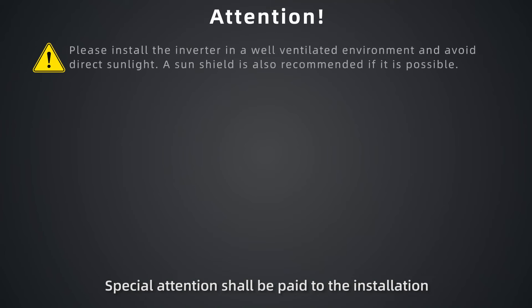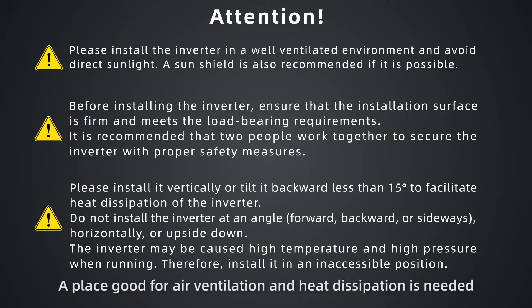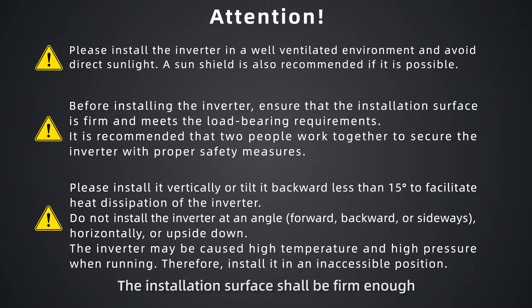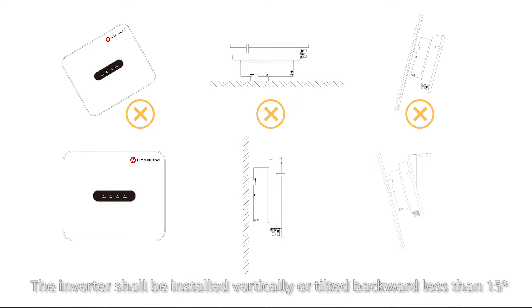Special attention shall be paid to the installation environment of the inverter. A place good for air ventilation and heat dissipation is needed, and it is recommended to install a sun shield. The installation surface shall be firm enough and meet the load-bearing requirements. The inverter shall be installed vertically, or tilted backward less than 15 degrees.